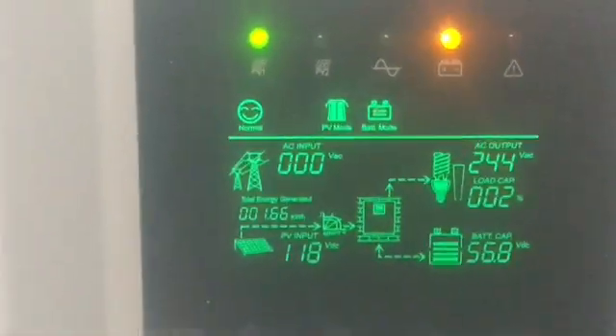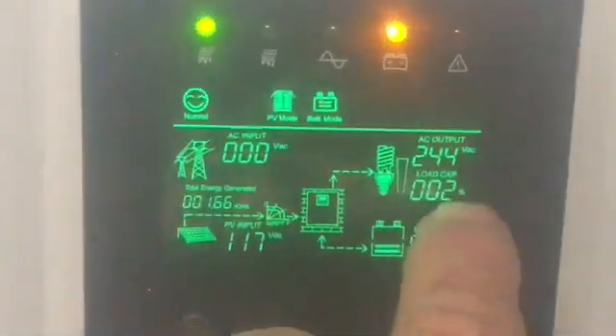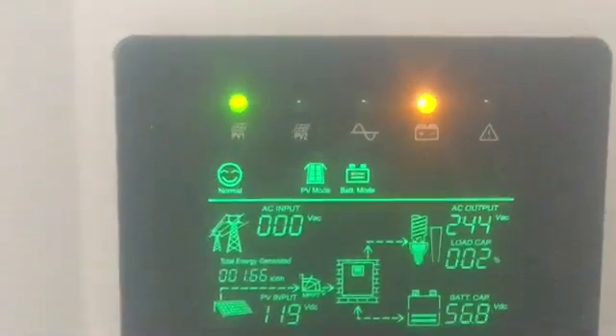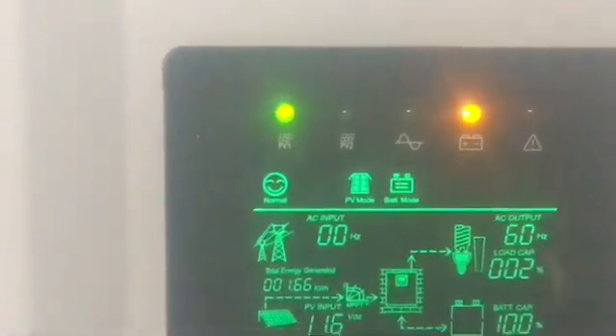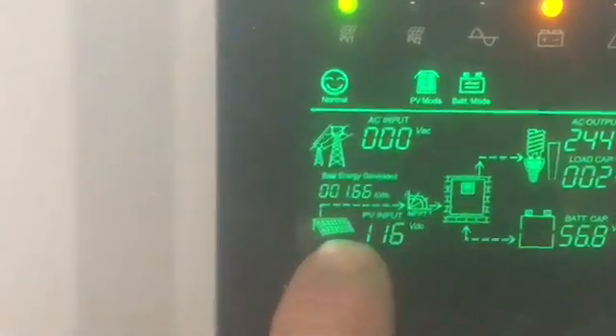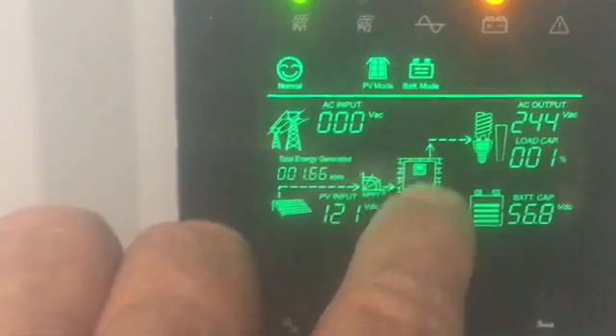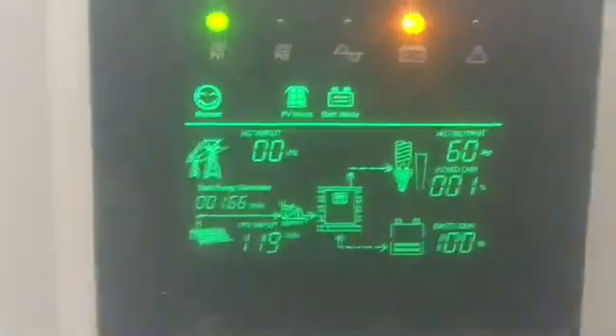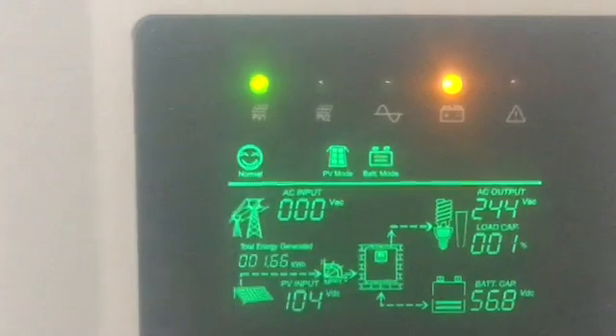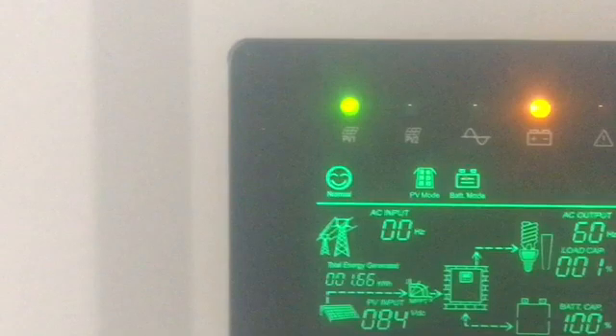Right here is the grid power and you can see no line coming in going into the inverter, because we're in PV mode. We have power going out — right now we're only using two percent of everything we've got. We're working off panels and some battery. We are generating right now — this is the PV input going into it, generating 116 to 119 volts going into the MPPT controllers into the inverter. The battery is sitting at around 100 percent, at 56.8 volts.